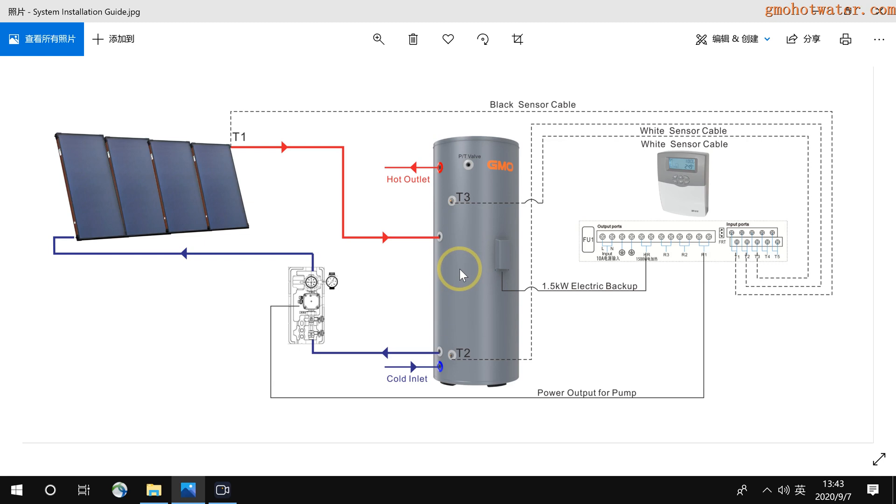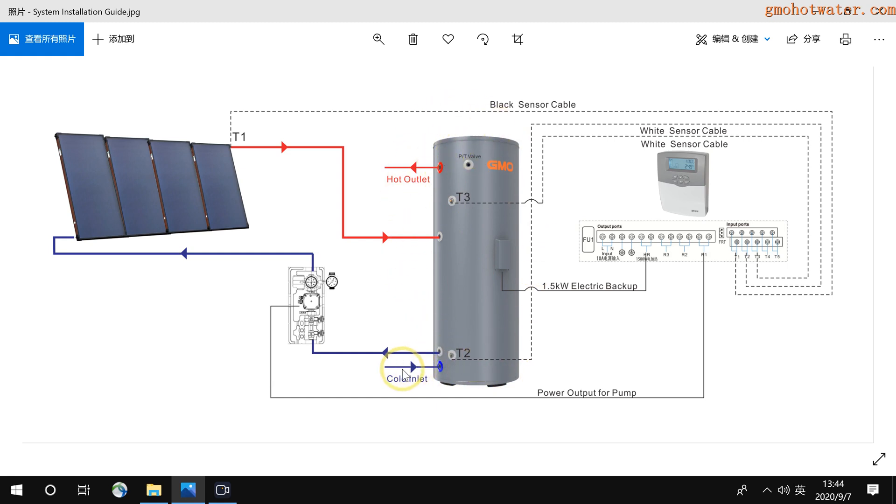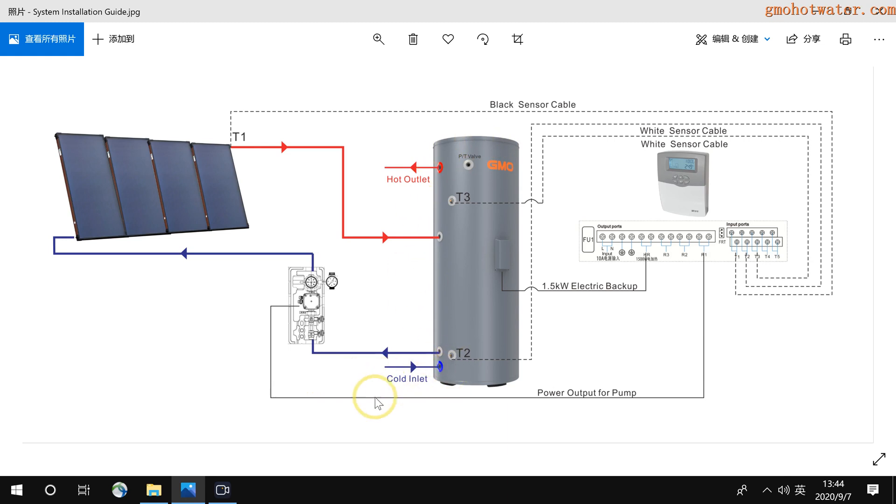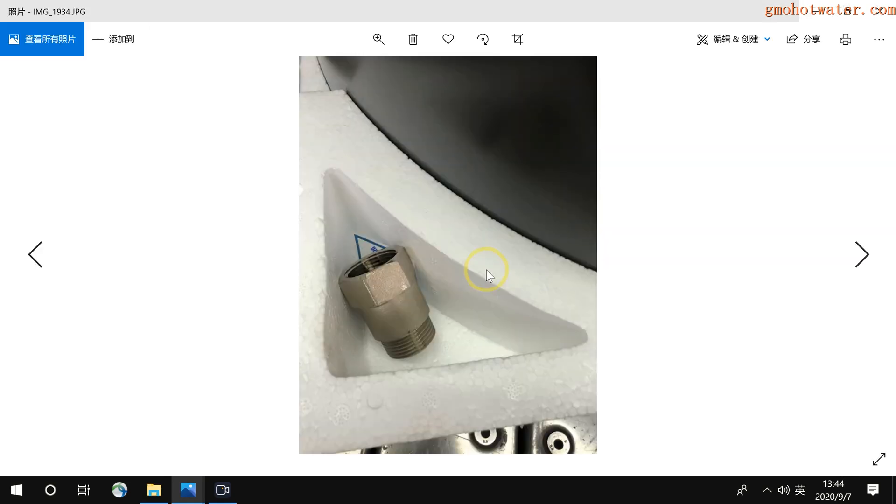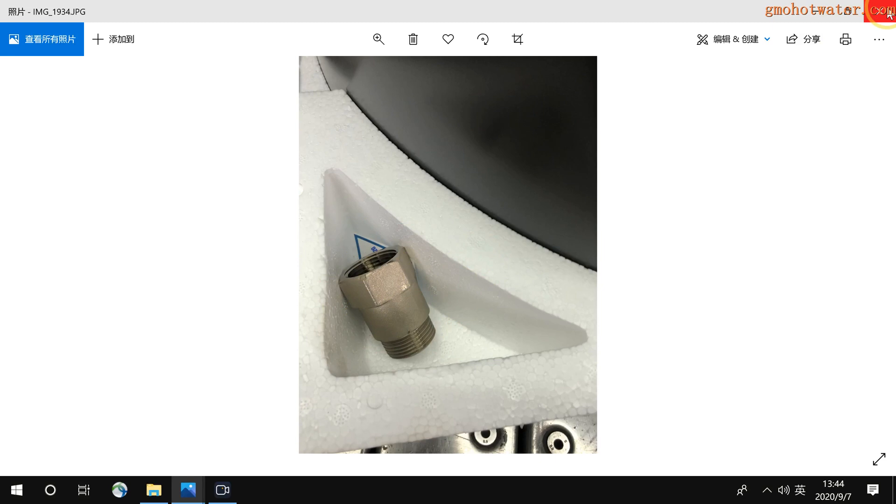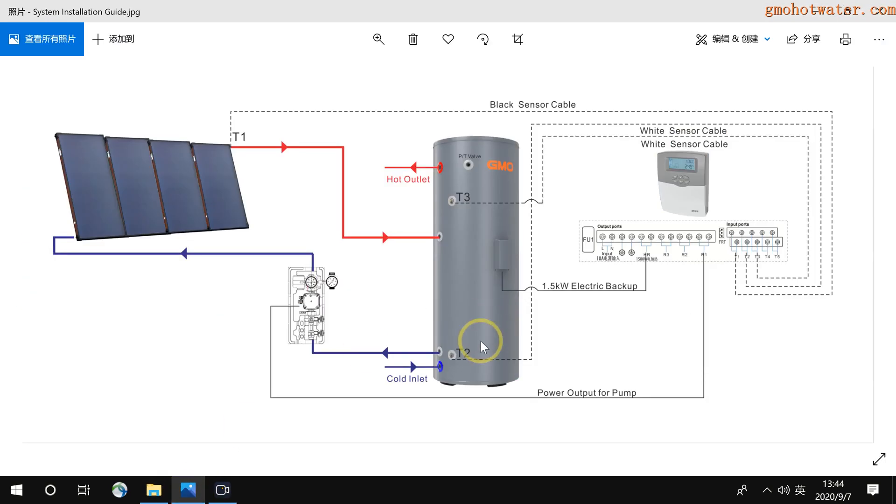Now I will introduce one part one by one. The first is hot water storage tank. Some attention for this tank when you install it. First, here is the cold inlet. In the water tank package, we have a one-way no-return valve. So before the cold inlet connection, you'd better connect here.